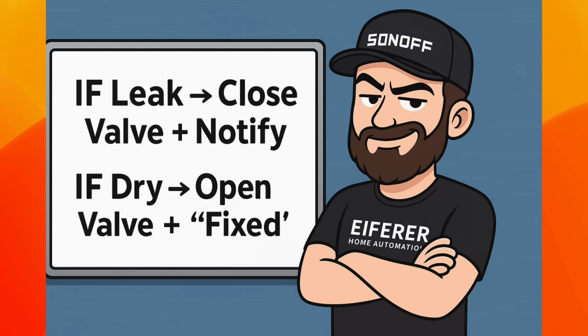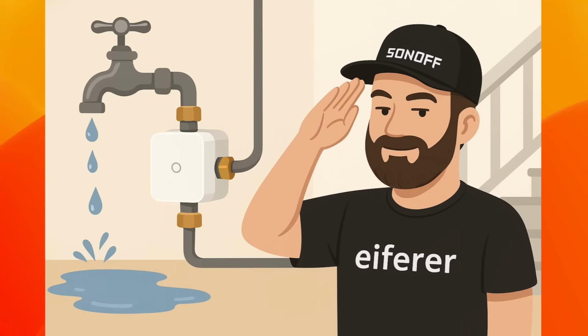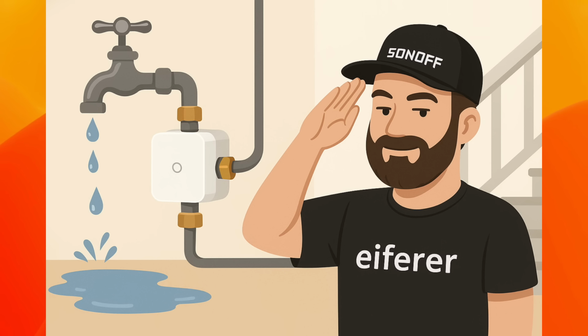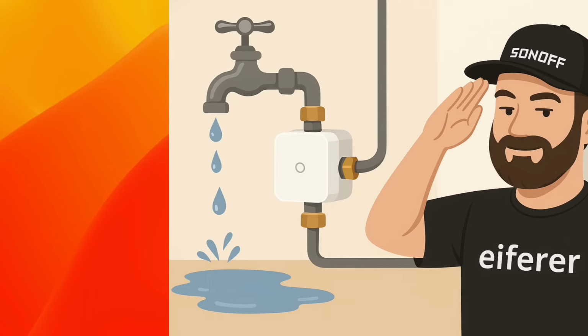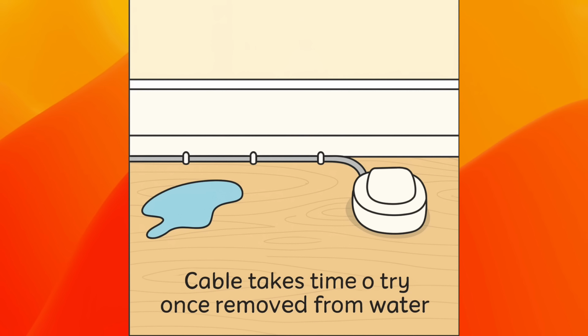How this prevents flooding. Make two simple rules. If leak, close valve plus notify. If dry, open valve, send notification, fixed. So if someone leaves a tap open during a water cut, when the water returns, the sensor detects the puddle and shuts the valve off before it becomes a stairwell waterfall, a week of downtime, damaged computers, and a higher insurance claim. Just a note on the sensor cable, it does take a bit of time to dry out, so you might need to remove the cable until it dries out to avoid the sensor from triggering again and again.